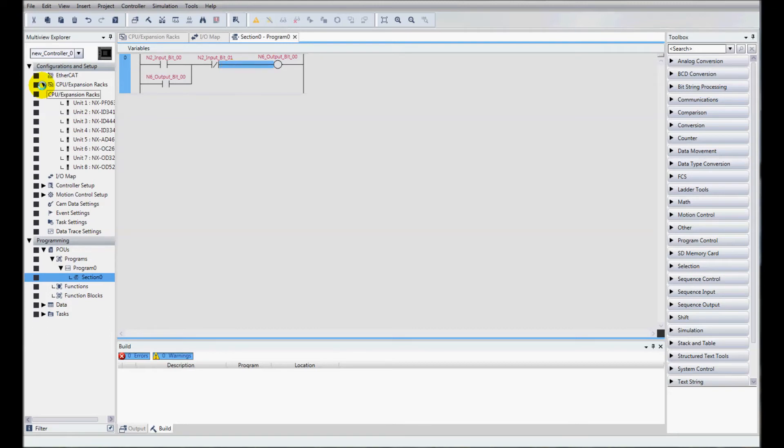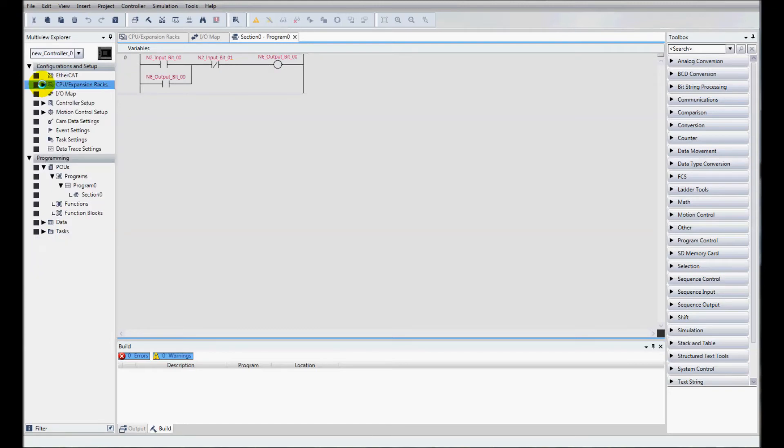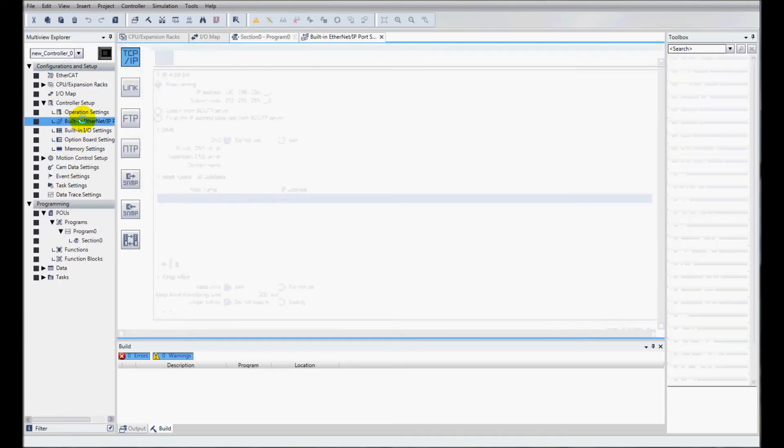At this point, I'm ready to download to my PLC. But let's first see what the IP address is for my controller. In this case, it defaults at 192.168.250.1. I'll come up to controller, communication setup. I've got a hub, and I'll type in that address, 192.168.250.1. I'll check my communications and it tests OK. I'll click OK and I'll go online.